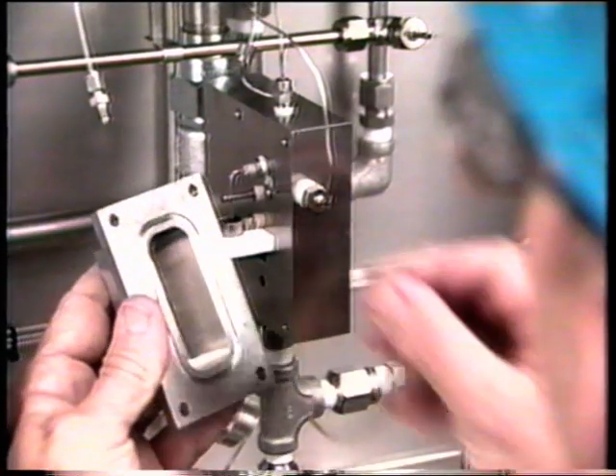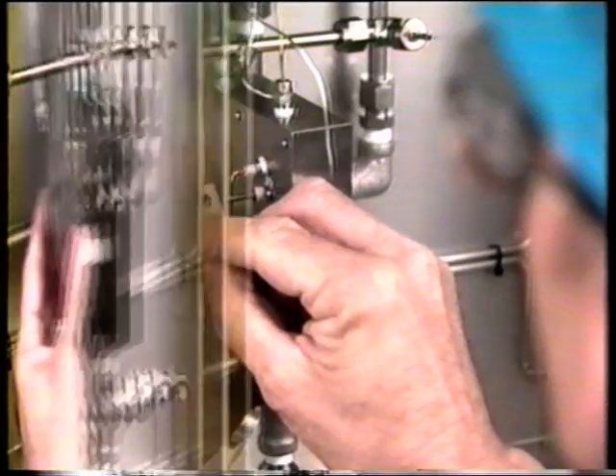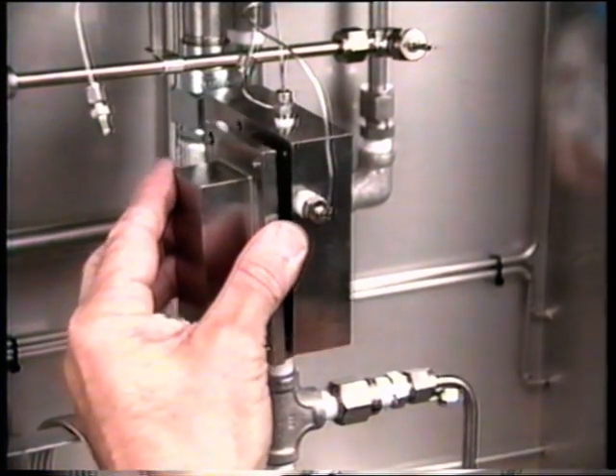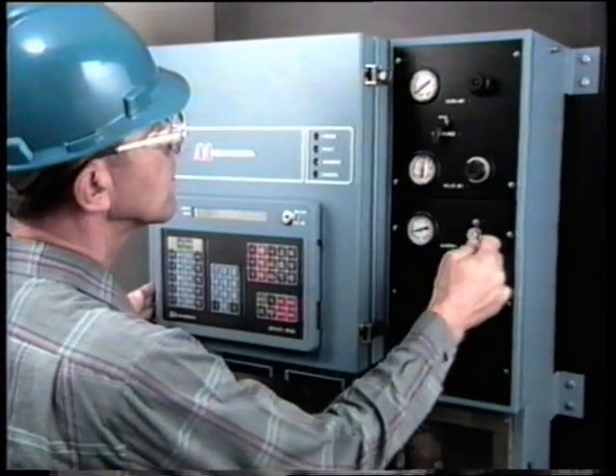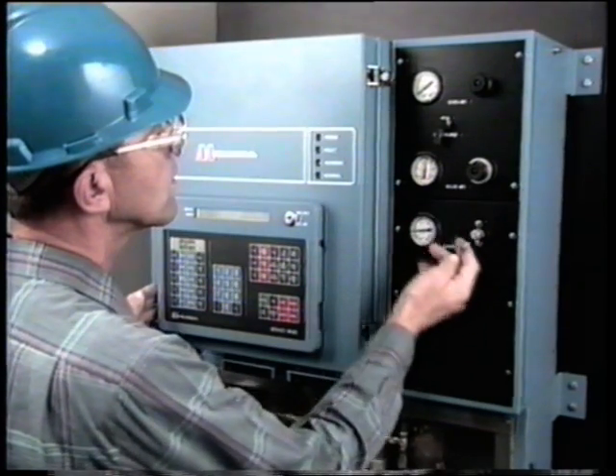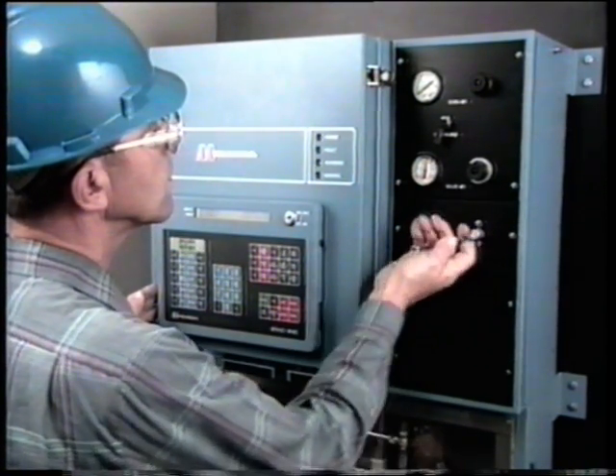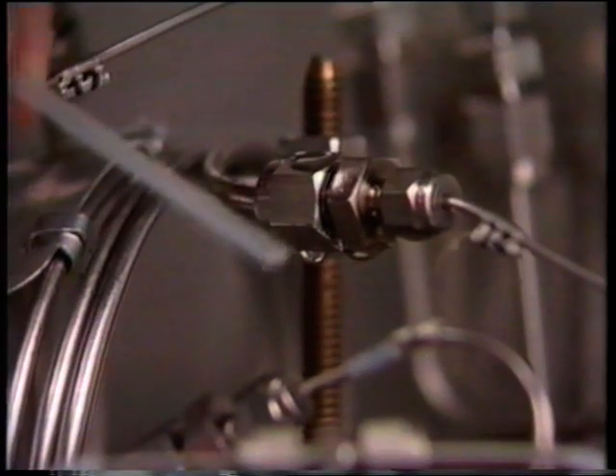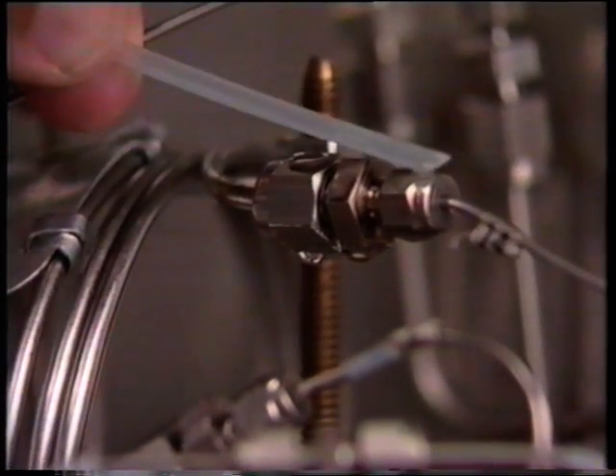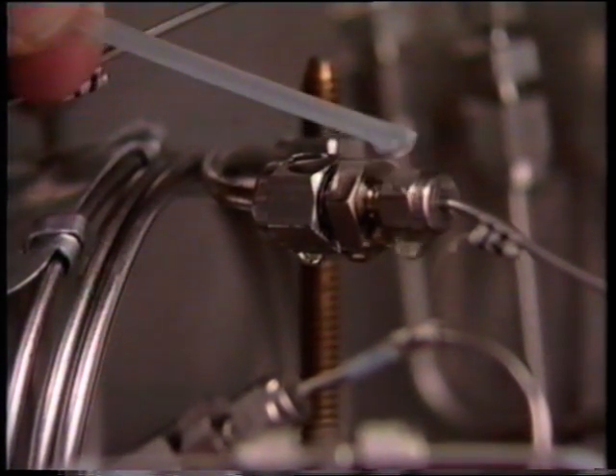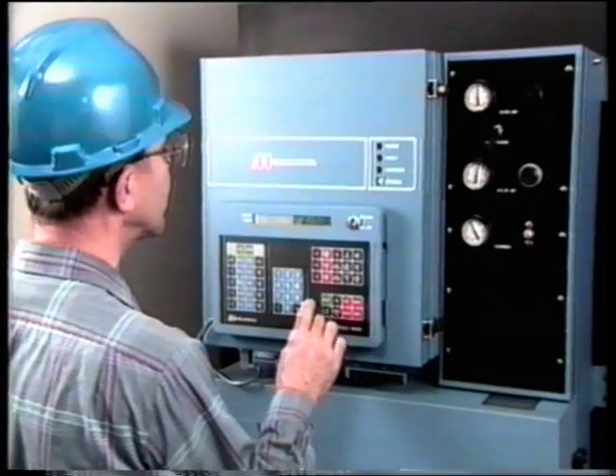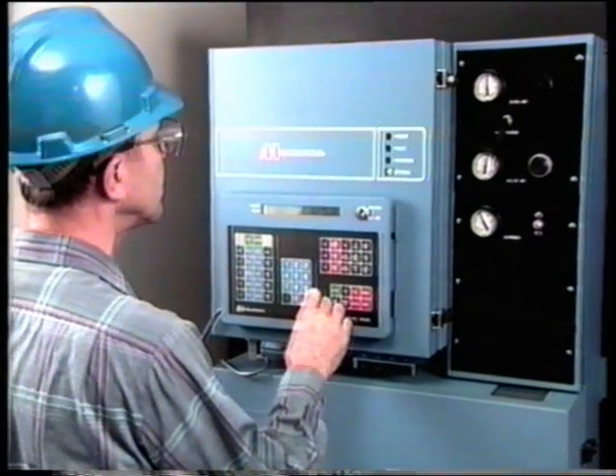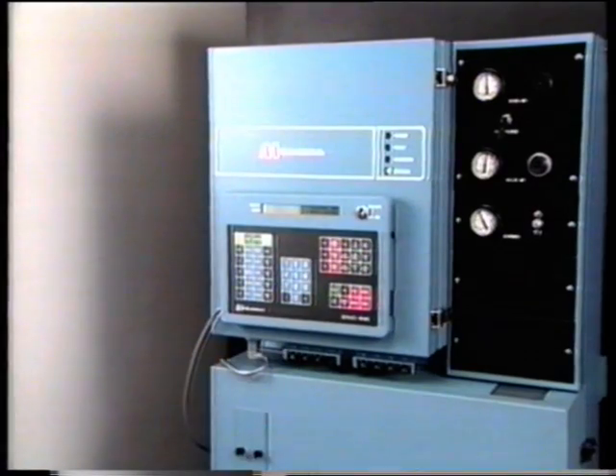Install the sensor cover O-ring in the sensor cover. Install the terminal cover and the sensor cover. Adjust the carrier, flame air, and flame fuel regulators to their proper settings. Leak check all the connections. Wait for the flows to stabilize and the lines to purge. Turn on the electrical power and restore the system to operation.